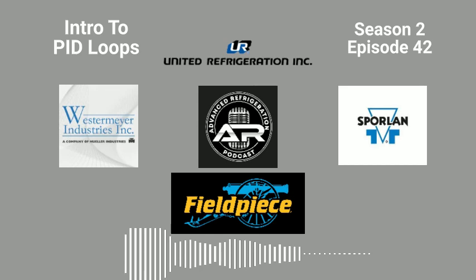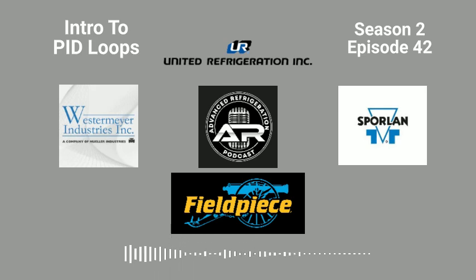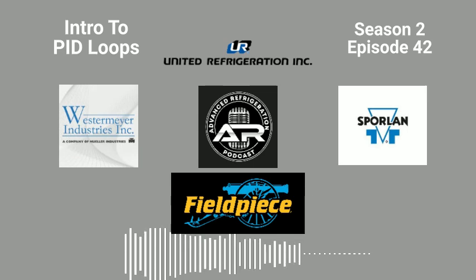That is one thing I like about Micro Thermo, their new condenser application has a summer and a winter set point. Same thing with their CO2 controls for the gas cooler and the flash tank. They have summer and winter PIDs, so you could change your PIDs for summer and winter. It allows you to dial it in so much tighter. Unlike Emerson and Danfoss, where you're kind of just stuck with what it is and you have to manually adjust it. They've already thought about this.